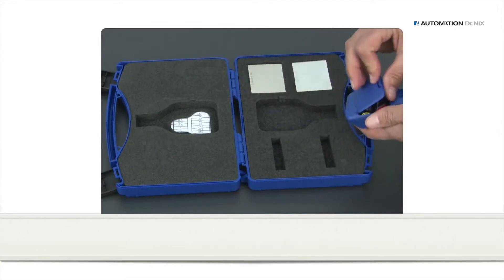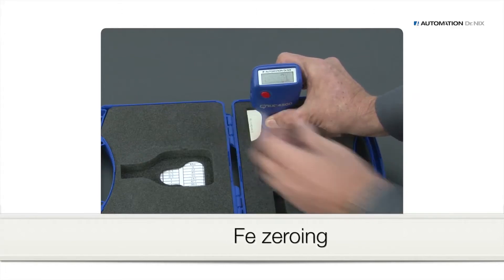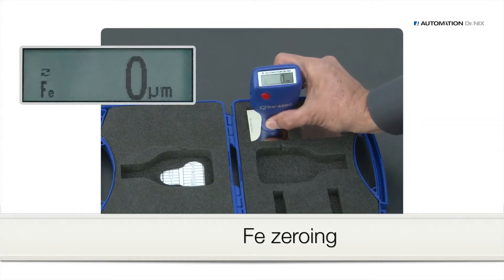To perform a zeroing of the gauge, put it onto the zero reference plate, here iron. Press red button. Lift gauge at least 10 cm or 4 inches up until the display shows zero.